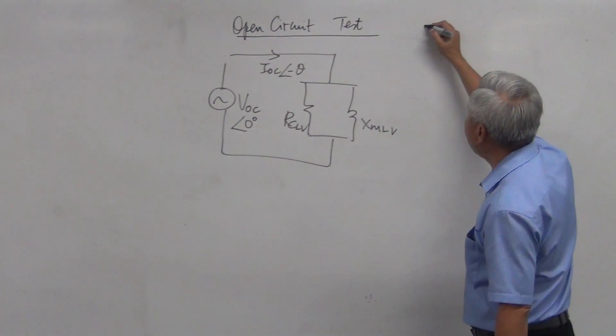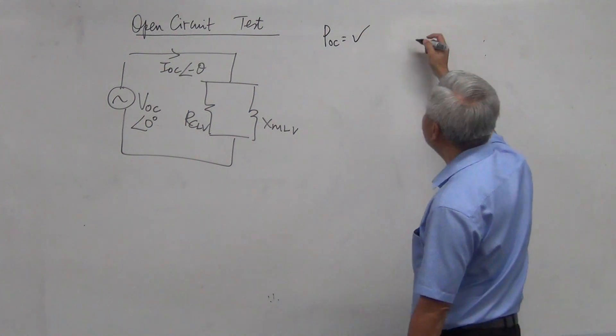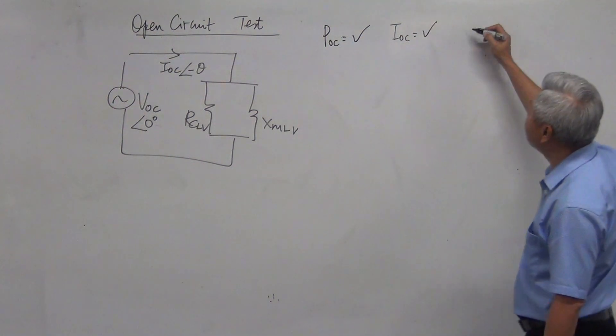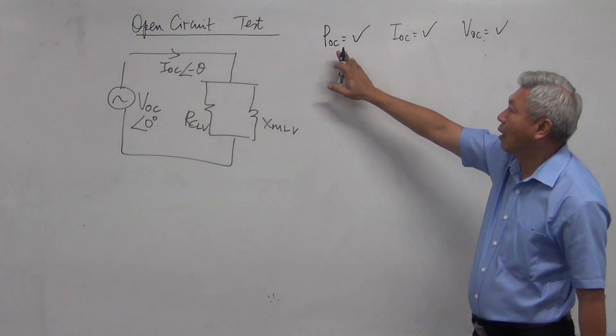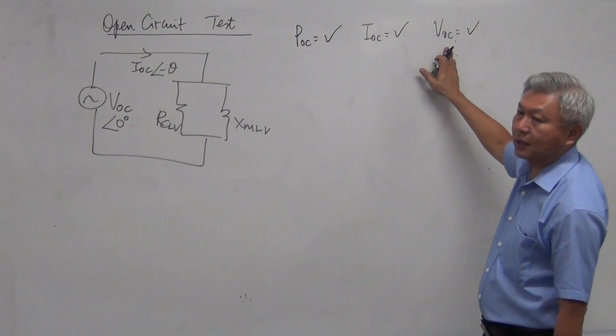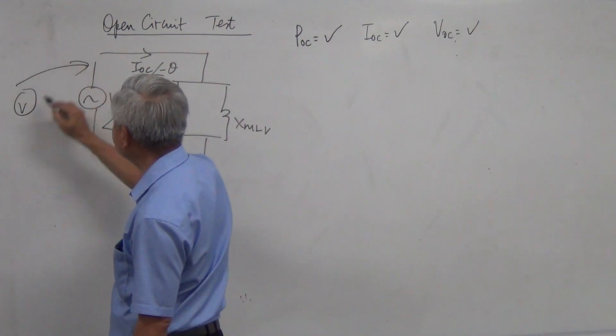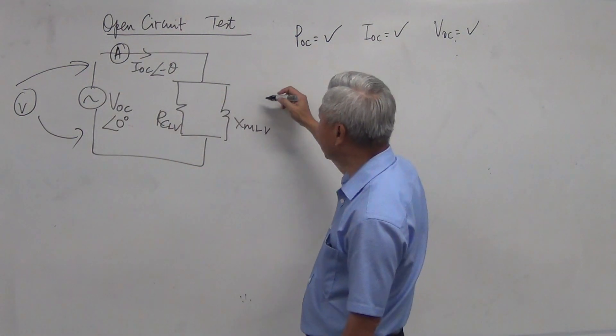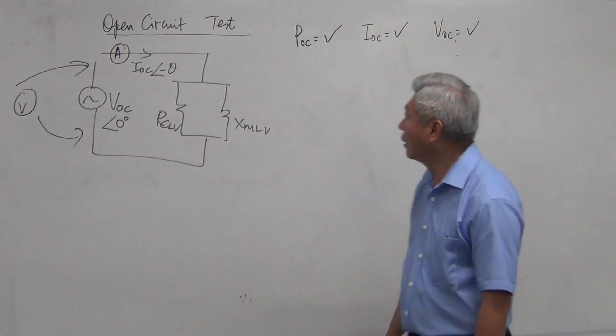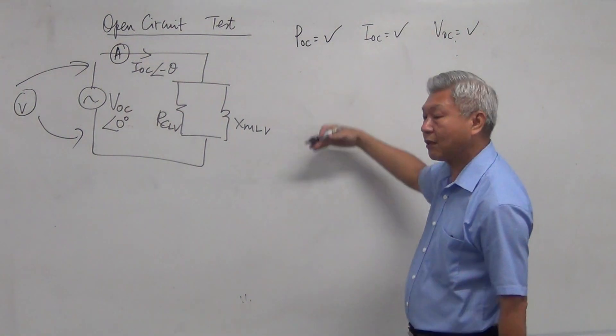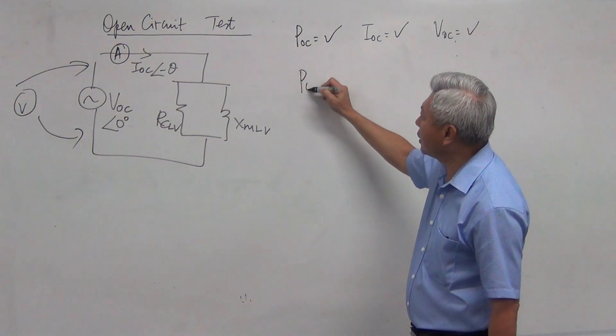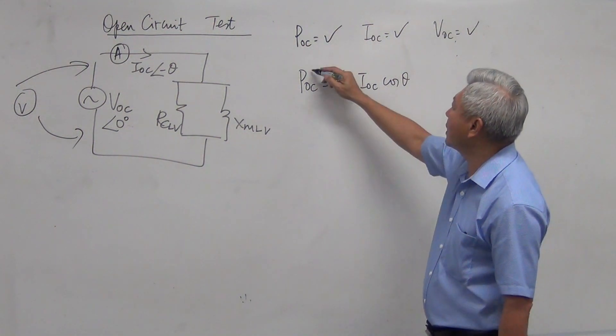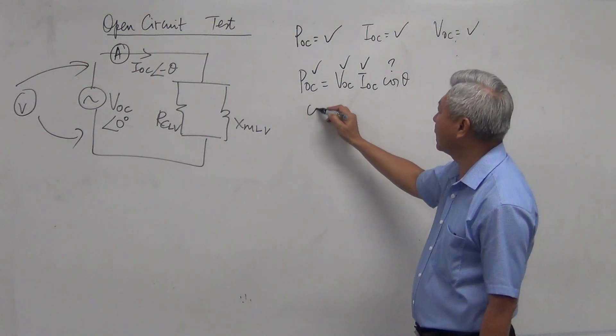Let's talk about the experiment itself. We have obtained the wattmeter reading, the ammeter reading, and the voltmeter reading — three meters: wattmeter, ammeter, voltmeter. The voltmeter is connected in parallel, the ammeter in series, and the wattmeter connected accordingly. The first step: use P equal to VOC times IOC times cosine theta. You have the power reading, the voltage reading, and the current reading — so cosine theta can be found.